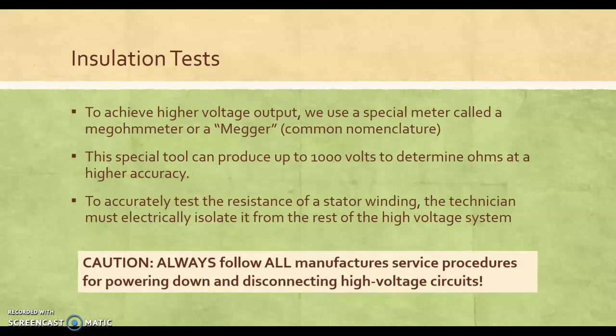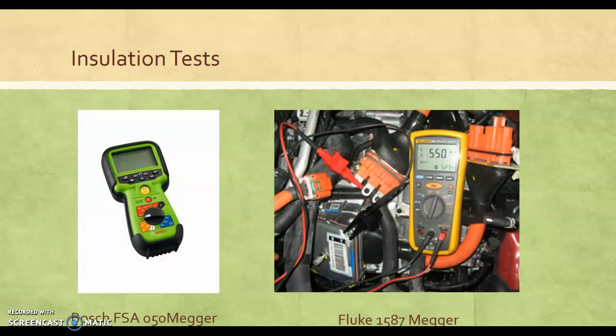Always follow manufacturer service procedures for powering down and disconnecting high voltage circuits, and remember to wait for those capacitors to drain and then perform your live-dead-live, which won't be in the manufacturer's recommendation, but I highly advise it. Here's two more tools for doing insulation tests. You've got your Bosch FSA 050 Megger, my preferred tool. I like it. It's a digital meter that shows us an analog graph, which is kind of nice.